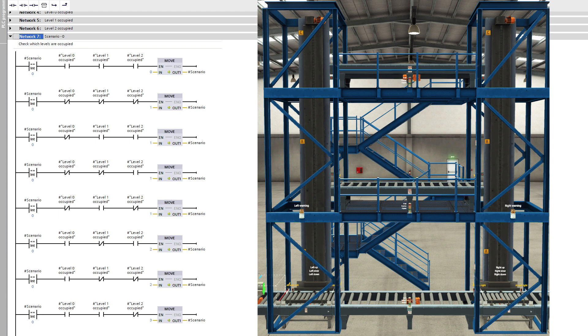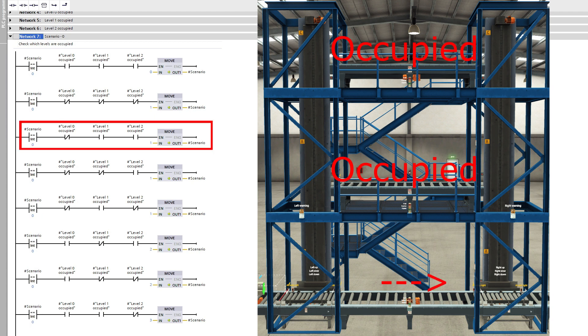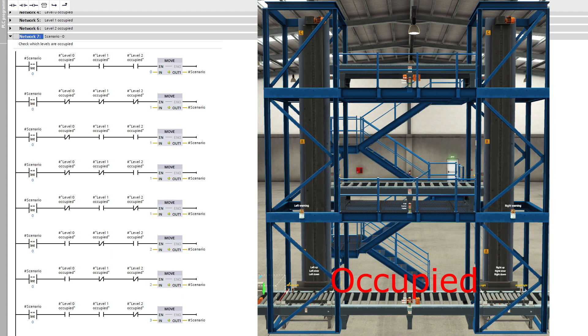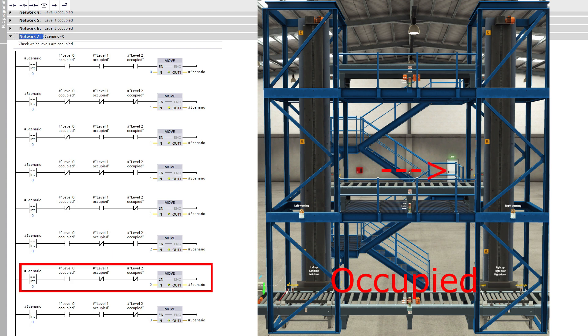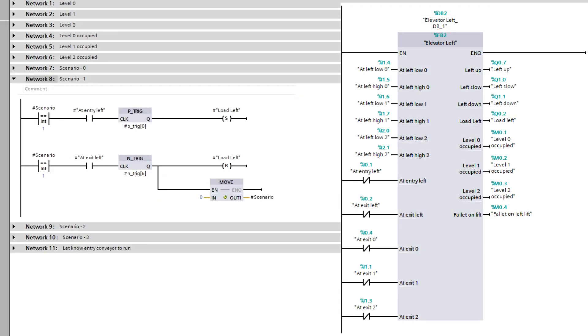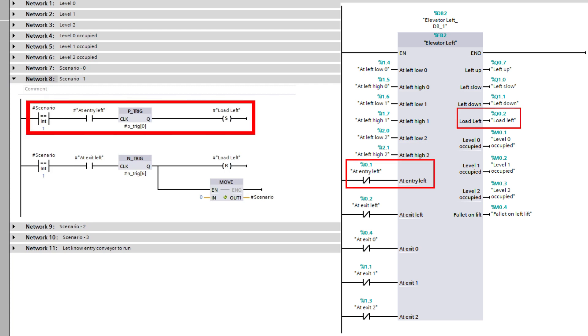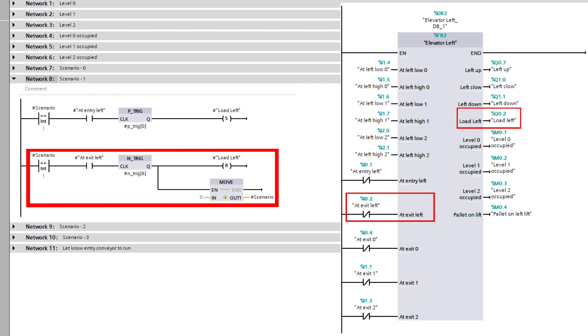In the next rung, I made it so that depending on which levels are occupied, different scenarios should happen. For example, if level 1 and level 2 are occupied and level 0 is not occupied, then it will choose scenario 1. When scenario 1 sets active, the lift will load the pallet and let it go until it passes the exit-left sensor at level 0.